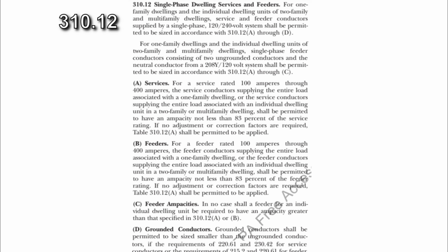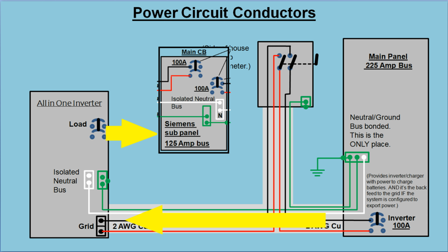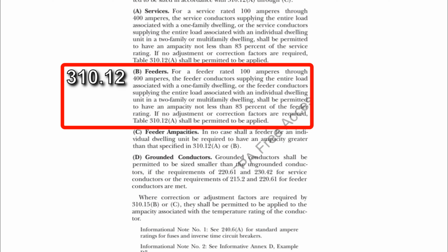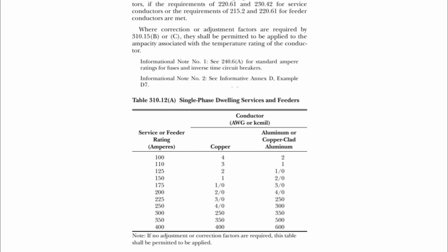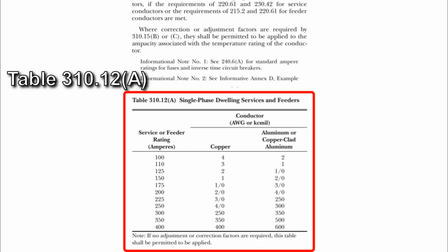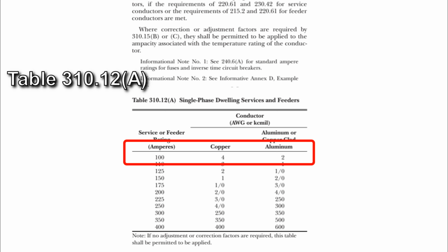Now, 310.12 refers to dwelling services and feeders, and while there might be an argument for calling this circuit a feeder, I'm not comfortable using the less rigorous requirements of 310.12 for this circuit, especially considering the feeder ampacity ratings allowed by Table 310.12(A). What do you think? Is 310.12 applicable to this circuit? It permits number 4 copper at 100 amps.